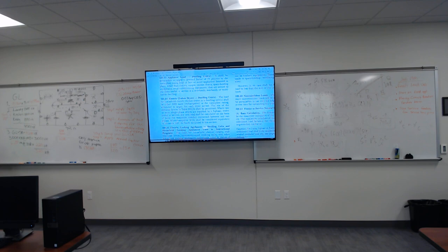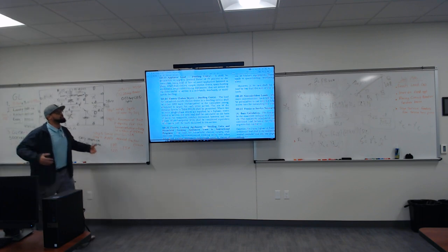The use of the demand factor in Table 220.54 shall be permitted. Where two or more single dryers are supplied by a three-phase four-wire feeder or service, the total load shall be calculated on the basis of twice the maximum number connected between any two phases. Kilovolt-ampere shall be considered equivalent to kilowatts per load calculated in this section. All right, so I'm going to basically break down the part that we need to understand, the first half. The second part, the three-phase part, we ain't worried about that because it's a residential home.